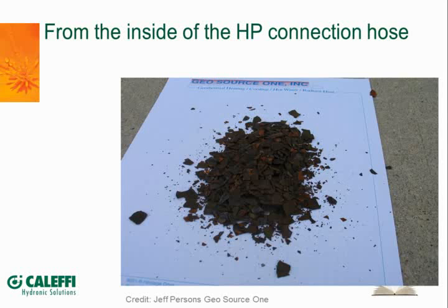The system this came from filled a 30-gallon trash can. Pump strainers kept plugging up, so we took them apart and flushed the system, using hammer drills on the sides and low points of the lines to agitate the material and get it to liquefy and flow out. We eventually got the whole system cleaned out, but it was quite a process collecting this material at the pump room, flushing it around the system, and separating it.